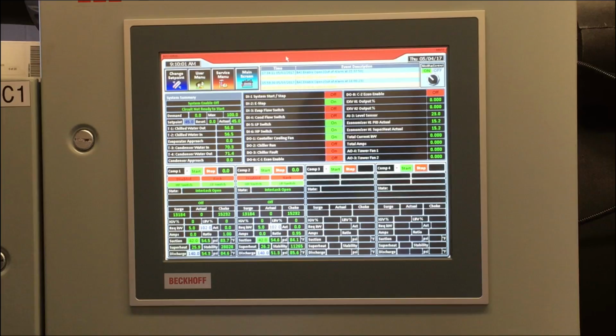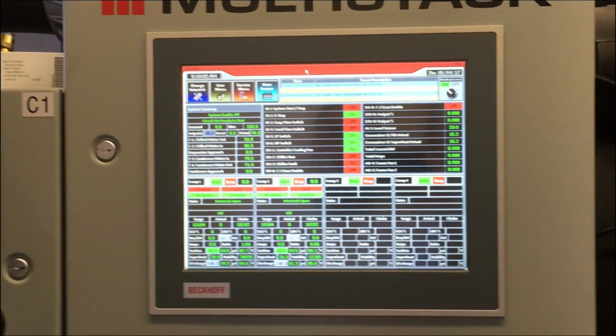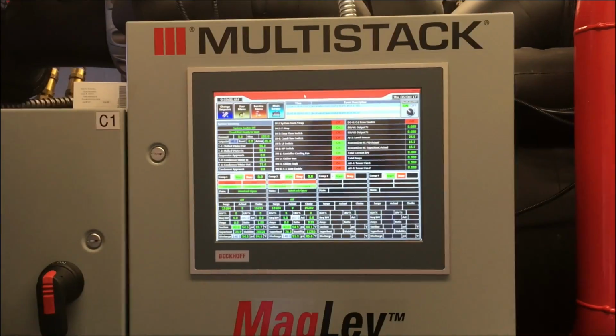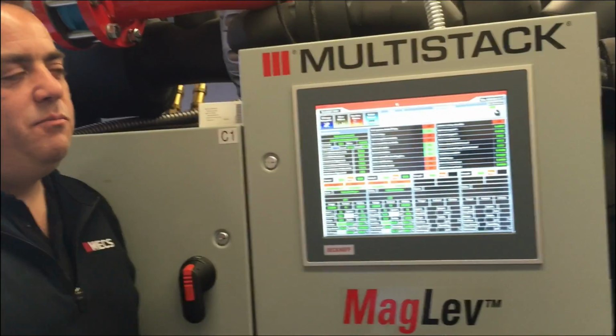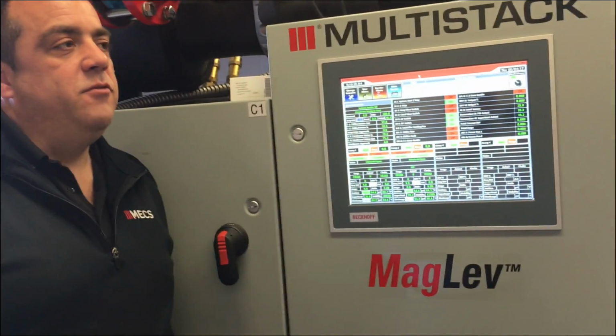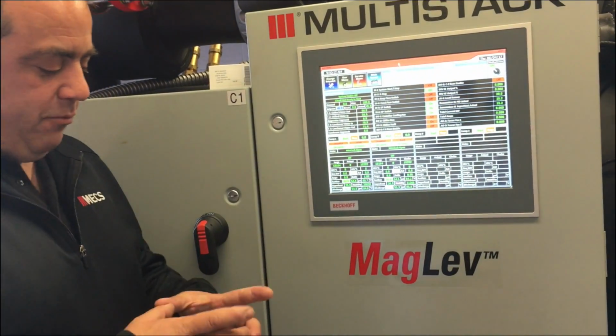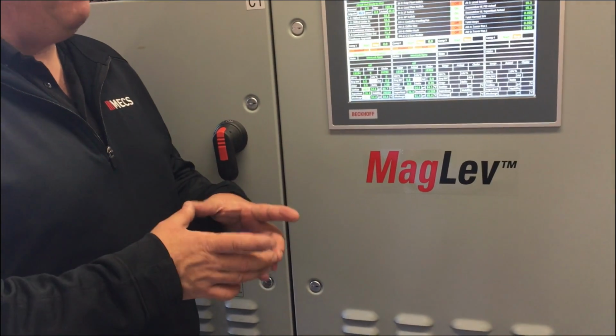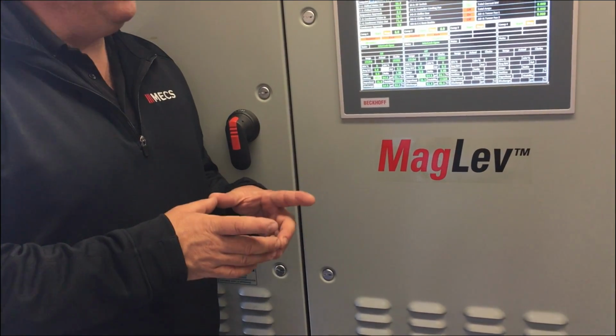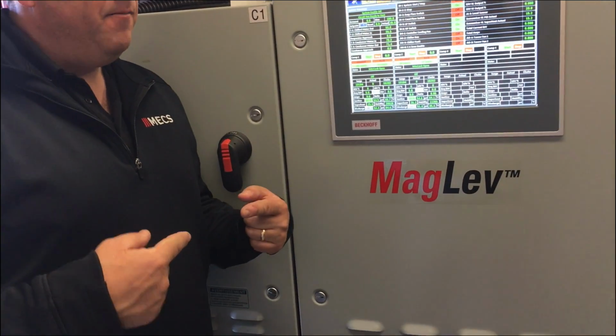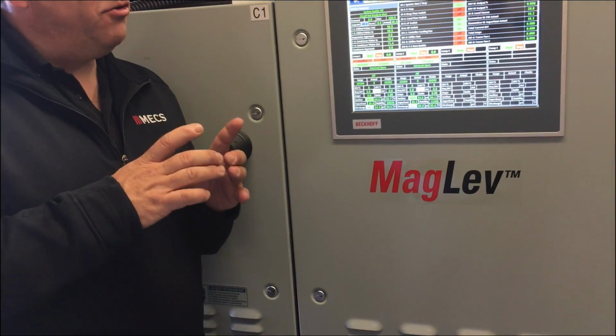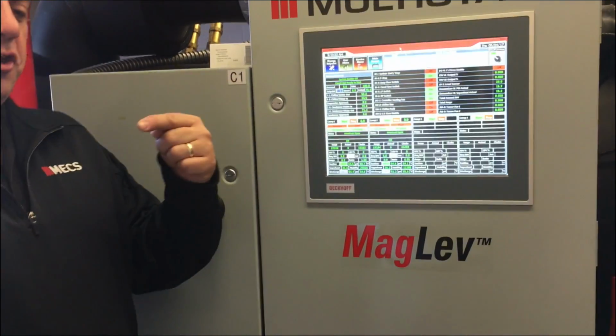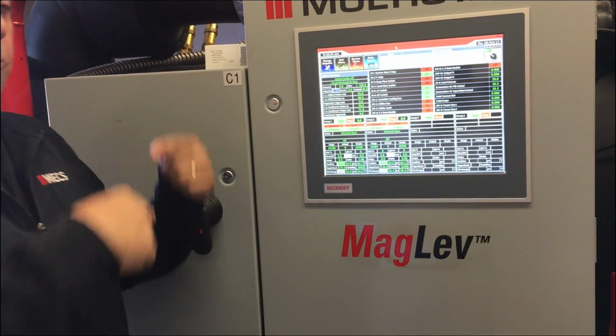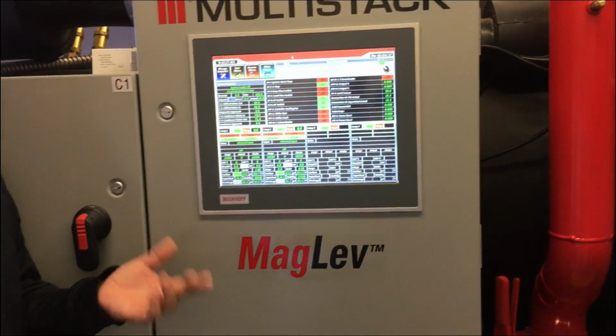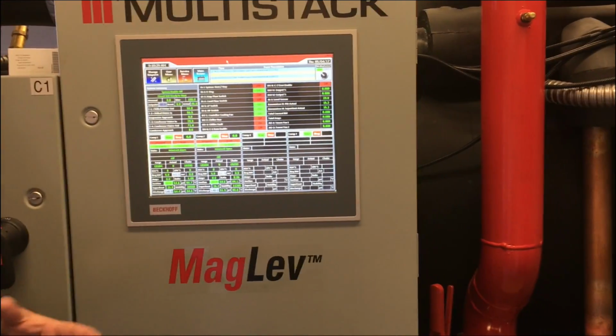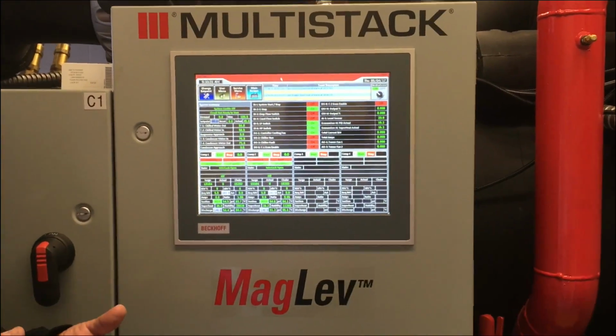So all the technology is maintaining that levitation with the magnets. It's an electromagnet that uses basically the theory of opposing magnets. So we take that round, we call it a bearing, even though it's just a magnet, it's a magnetic bearing, and we energize it in all directions so that we push on that shaft so that it stands up in the middle of that circle. Like a positive negative, when you push on a magnet, the other one pushes away. Yeah. We're using that same principle, but we do it with electricity, and that's how we stand that up in the middle of that shaft, in the middle of that bearing.